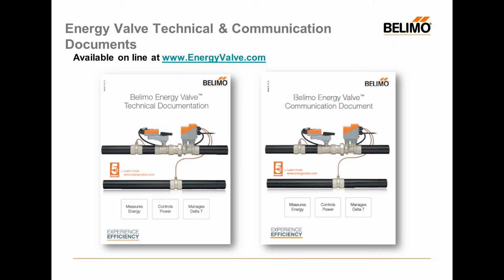But at the maintenance level, you cannot change the settings in the Energy Valve. So that is to say, you can't reconfigure or reprogram the Energy Valve at the maintenance level. That would require admin user credentials to do any reprogramming. Those credentials or that password you can get either from tech support or again from your local district sales manager.